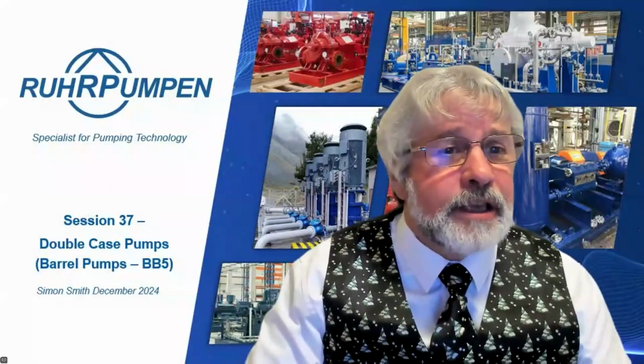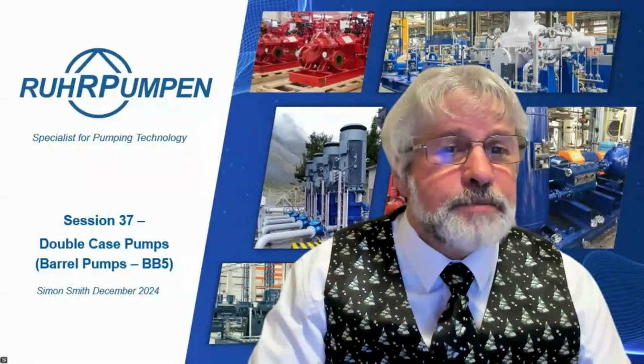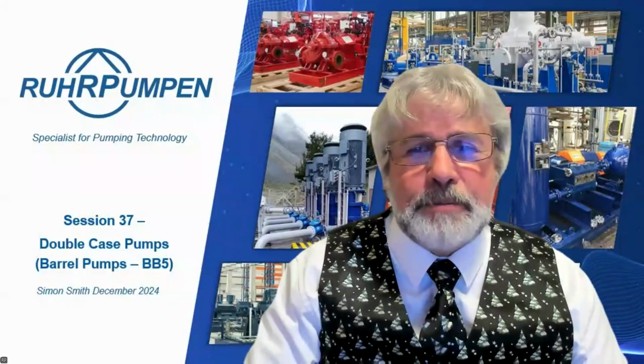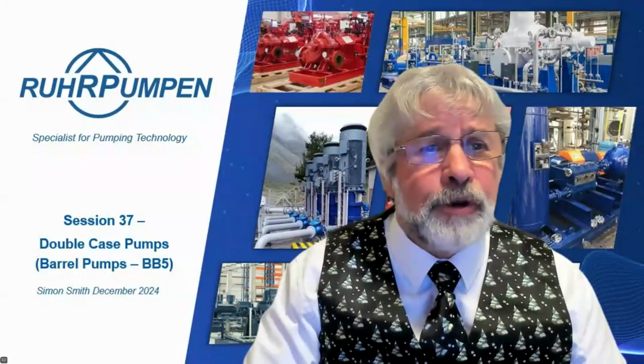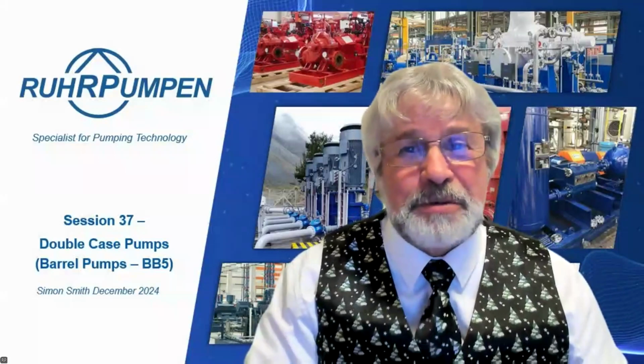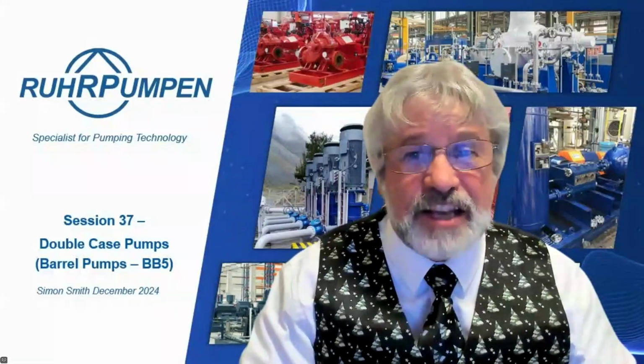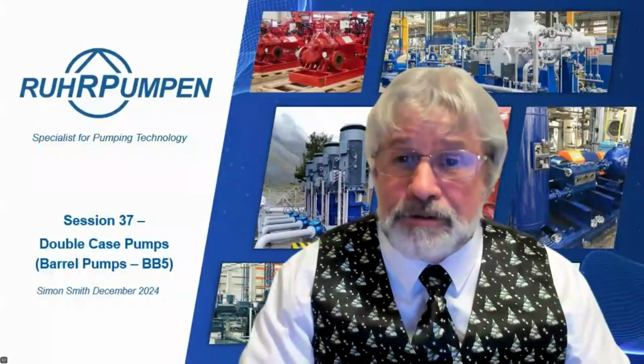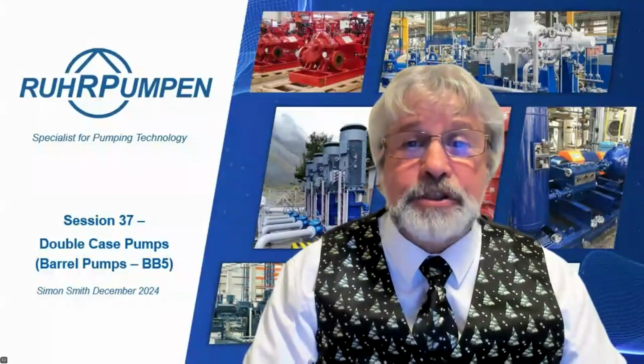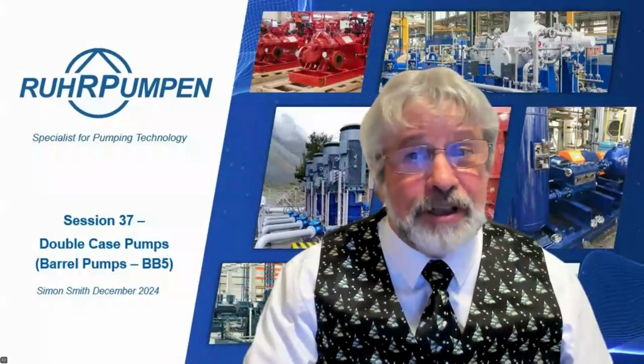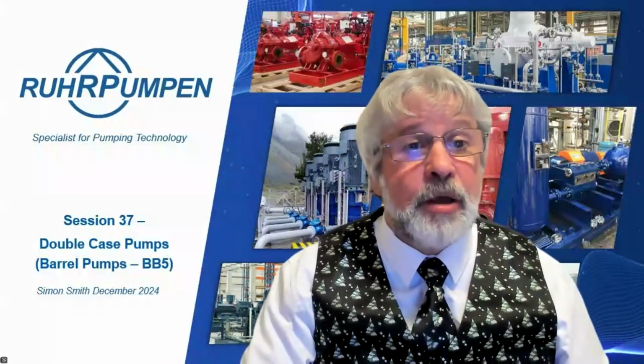Anonymous attendee has said, VFD versus fluid coupling, which one is best technically and cost-wise? VFDs have come on leaps and bounds. I would have said, 20 years ago, the fluid coupling was ubiquitous, just about everywhere. Nobody would use a high tension VFD, but VFDs have come on leaps and bounds, and you can now buy good, reliable, not too expensive VFDs for high voltage motors. But it is a balancing act, really, and I would always look to consider both the fluid coupling and the VFD for any application.